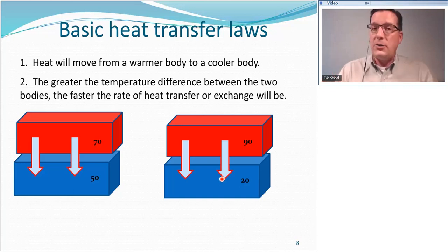Whenever we're talking about transferring heat, which is all that we're talking about when it comes to heating systems, right? Whenever we're talking about transferring heat, we're always talking about a quantity of heat energy in BTUs over a period of time. So it's always described as BTUs per hour. That's the standard description of the rate of heat transfer. BTUs per hour. The total amount of BTUs transferred is not as important as the rate of transfer, BTUs per hour.